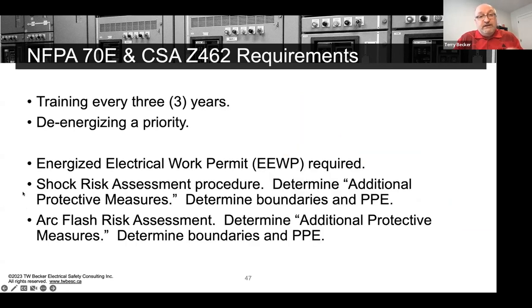Training every 3 years, de-energizing is a priority. That's quite clear in 70E and Z462, and I promote that. But we need to sort this out because people say, "Terry, we can't do any energized work." Well, 70E and Z462 don't say that. We want to eliminate the repair and alteration and do justified diagnostics and isolation-related work tasks, and we need to operate energized electrical equipment to, again, further assess the worker's exposure related to the work task inventory that you create.